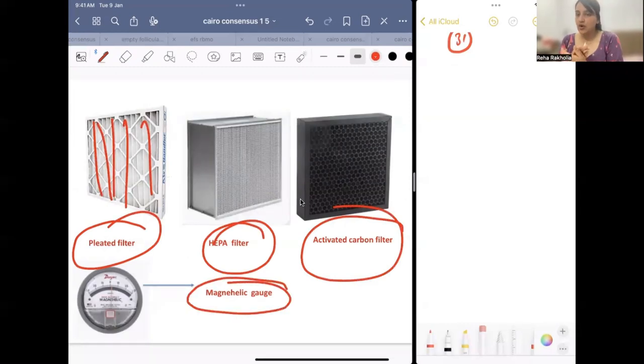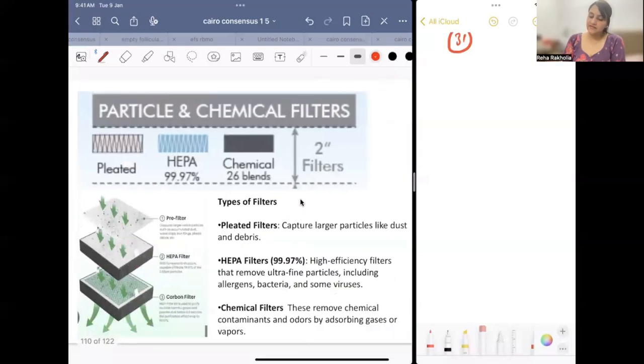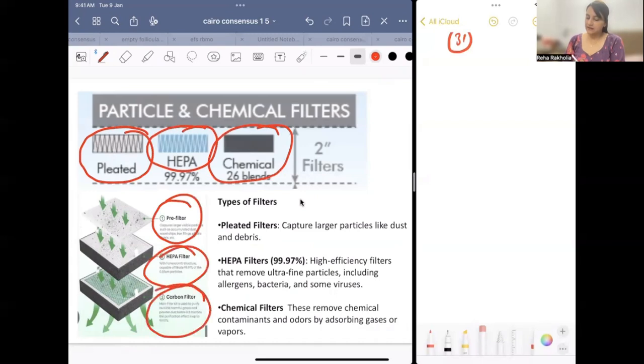magnehelic gauge, which tells about the pressure difference between the input air and output air, so that we can know if the filter is working efficiently or not, if there is a block in the filter or not. With this, we can tell. Then see, first air will go through pleated filter, then HEPA filter, and then chemical filter. Again, pleated filter, HEPA filter, and carbon filter.